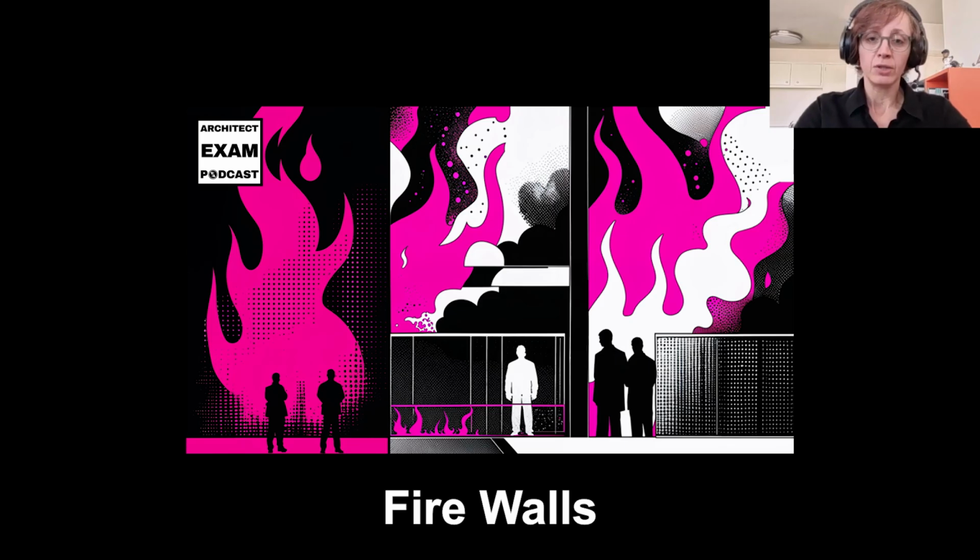With the characteristics of the firewall, we have to remember that it's going to have the highest fire resistance rating, and that's typically between 2 to 4 hours. It has complete vertical continuity. As mentioned, the firewall starts from the foundation of the building and goes all the way up continuously past the roofline by 30 inches, which is the code minimum for that parapet. And the purpose of that, again, is fire separation.